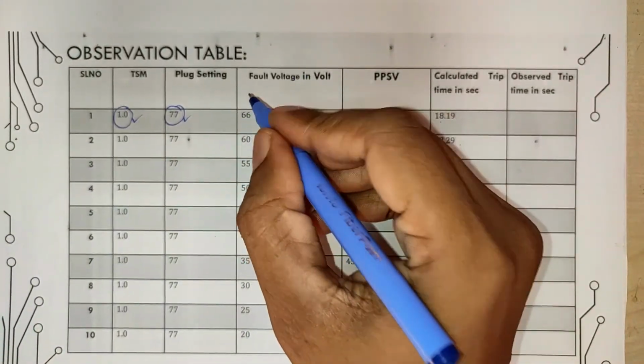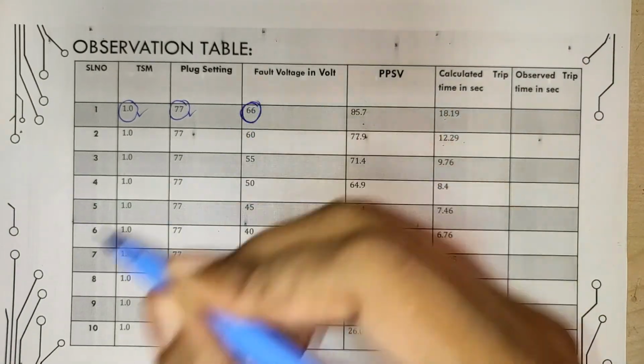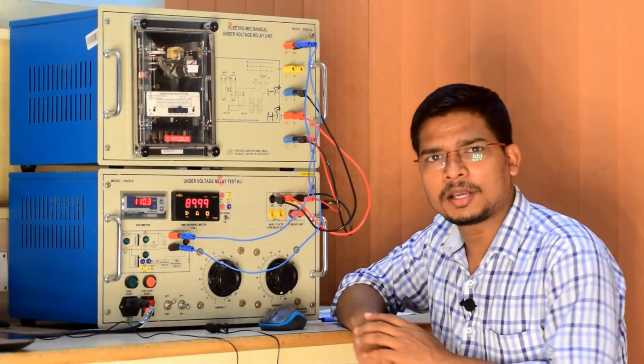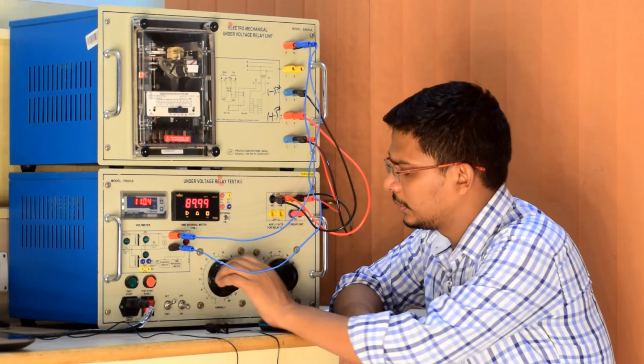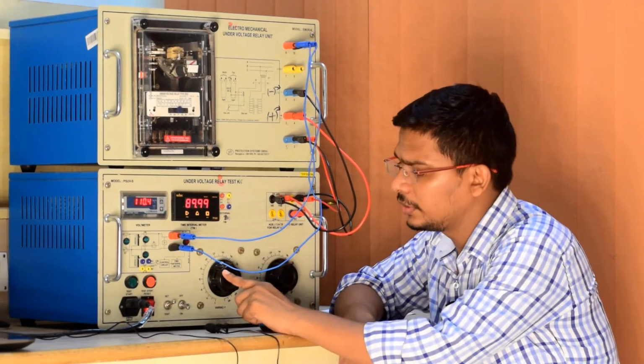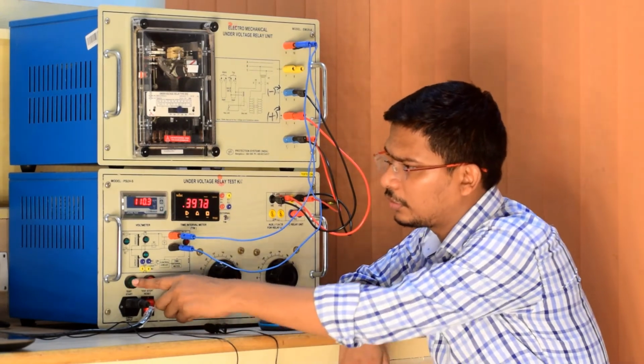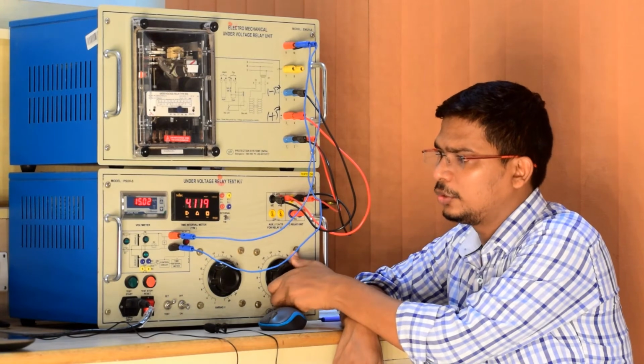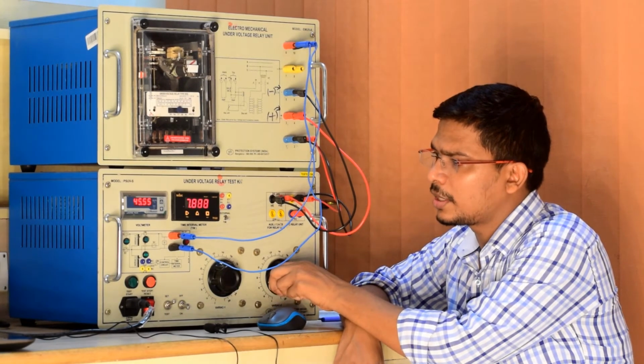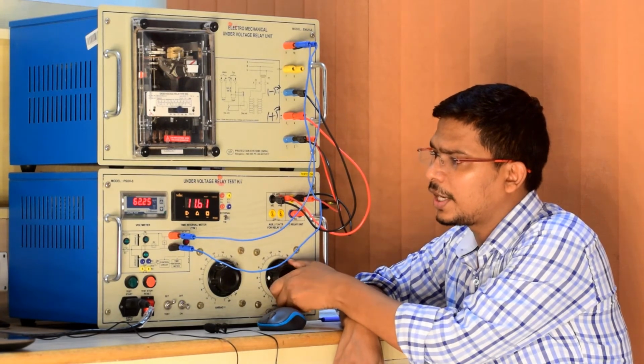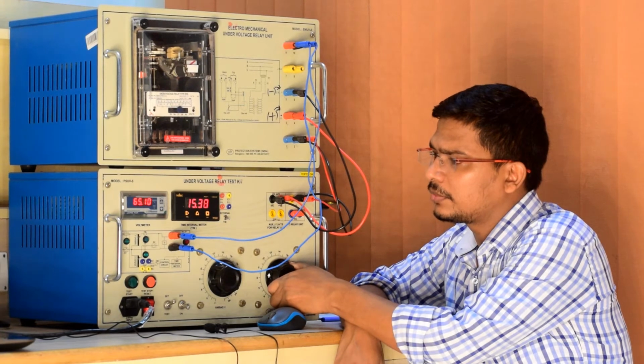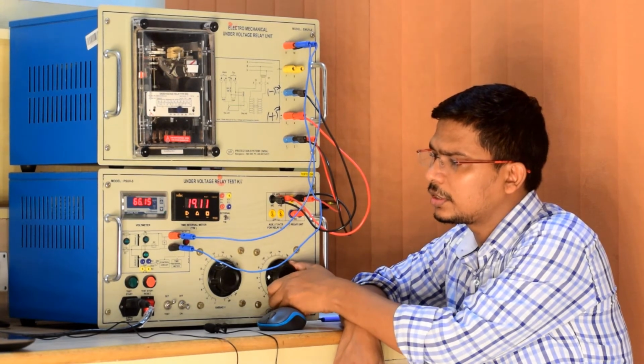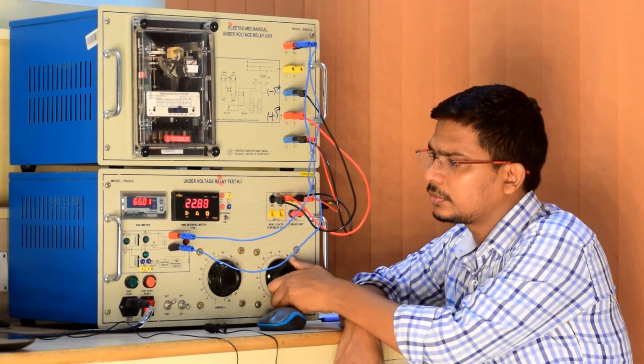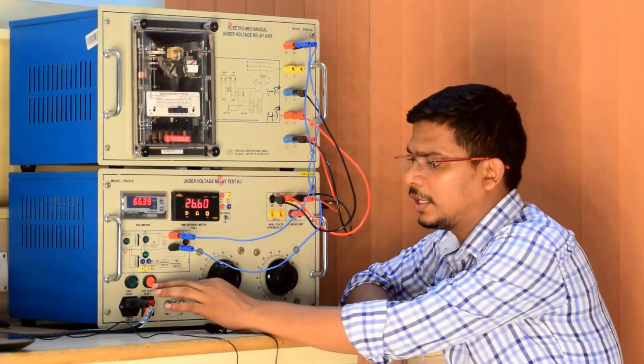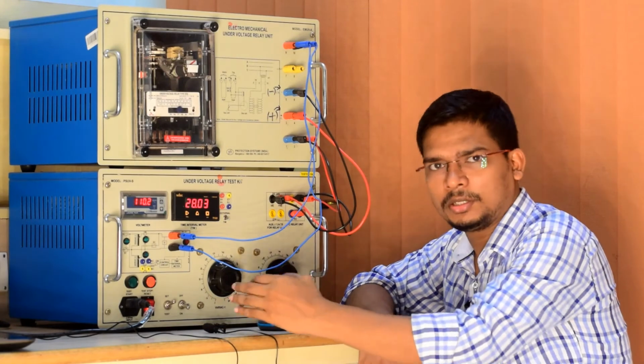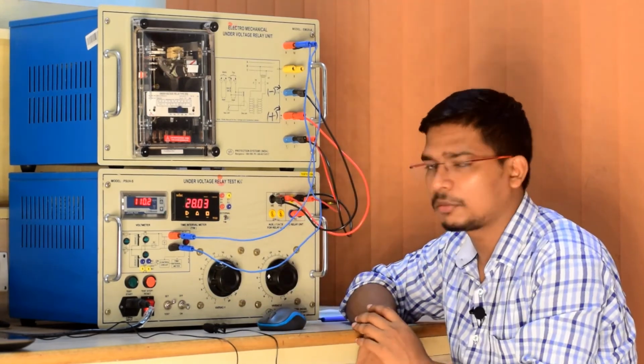As per the observation, we have to apply 66 volt as the fault voltage. So here you have to apply 66 volt. We will follow the procedure. This is 0, already we have given 110 volt, and this is in set mode. We have to turn on the circuit breaker and give 66 volt using Variac 2. So 23.86, 37, 45, 53, 56, 59, 62, 63, 65, 66, little more, okay. So 66 we have applied right now. After that we have to turn off the circuit breaker. After turning off the circuit breaker, 110 volt is applied, and the relay is coming to its normal operating mode.